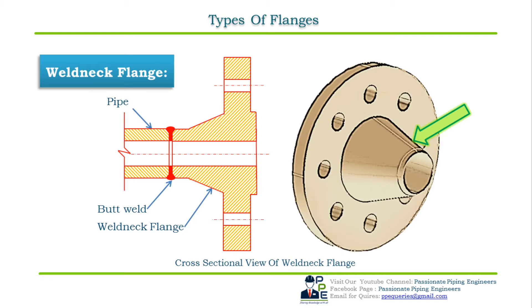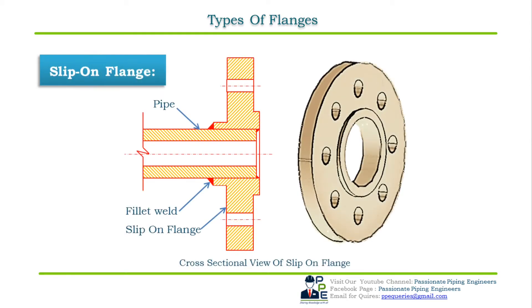Because of this matching ID, there is no restriction of flow; therefore turbulence and erosion are eliminated. Weld neck flanges are used in large bore sizes (about 2 inch NPS and above) and in severe service applications — high pressure and high or low temperature services — that require unrestricted flow of the fluid conveyed by the piping system. They are installed by welding the pipe to the neck (hub) of the flange, which allows transfer of stress from the flange to the pipe itself.